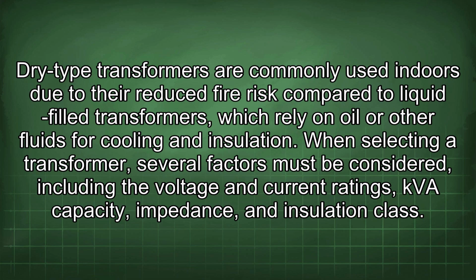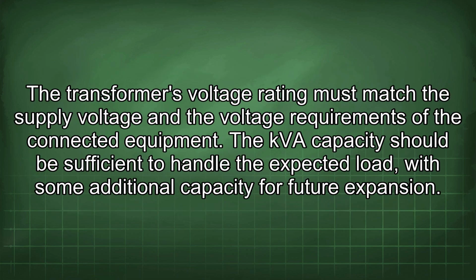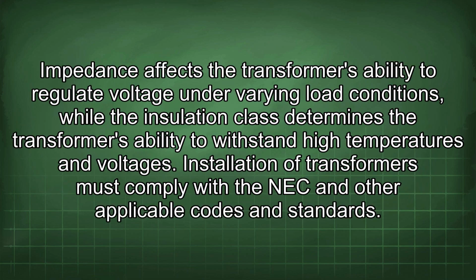When selecting a transformer, several factors must be considered, including the voltage and current ratings, kVA capacity, impedance, and insulation class. The transformer's voltage rating must match the supply voltage and the voltage requirements of the connected equipment. The kVA capacity should be sufficient to handle the expected load, with some additional capacity for future expansion. Impedance affects the transformer's ability to regulate voltage under varying load conditions, while the insulation class determines the transformer's ability to withstand high temperatures and voltages.